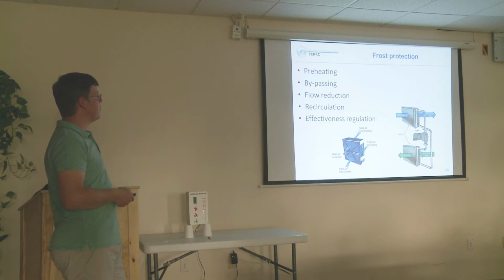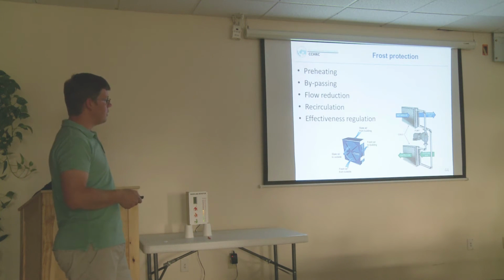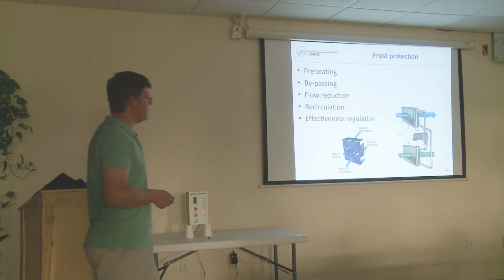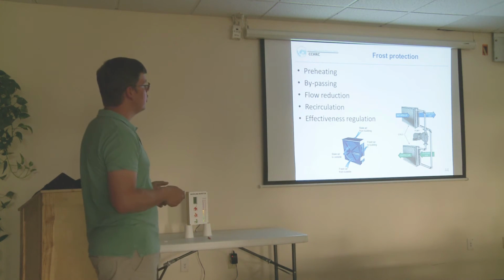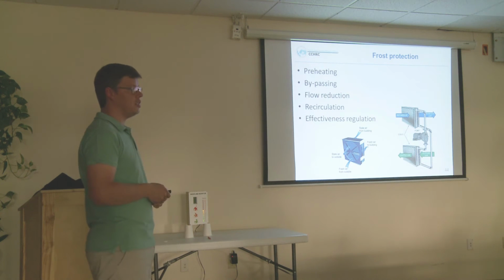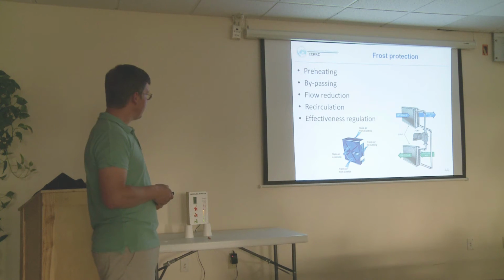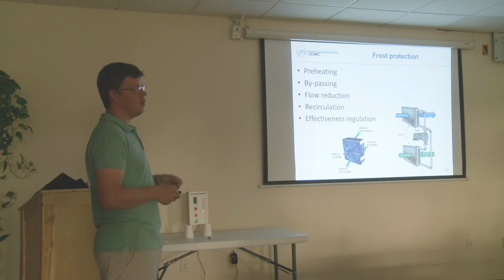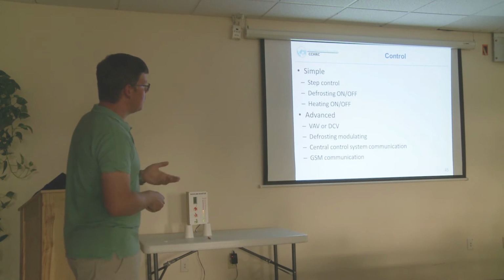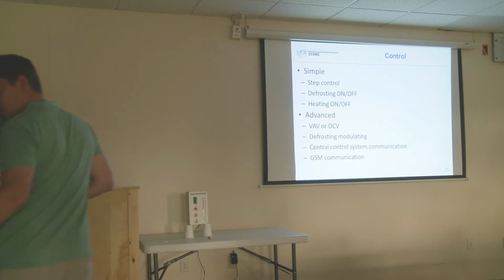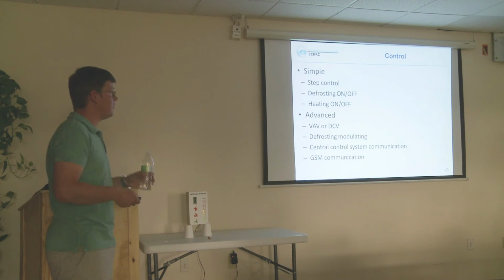Another way to protect from frost is regulation of effectiveness, and these two heat exchangers can do that. You can either stop the rotor, or you can slow it down so there's not so much heat exchange, or you can regulate the speed of the pump. Or actually in this system you could have a little heater here, so that would even heat the glycol to melt the ice formation if there is any. When it comes to controls of the ventilation units, there can be simple ways to control them or some advanced ways to control them.